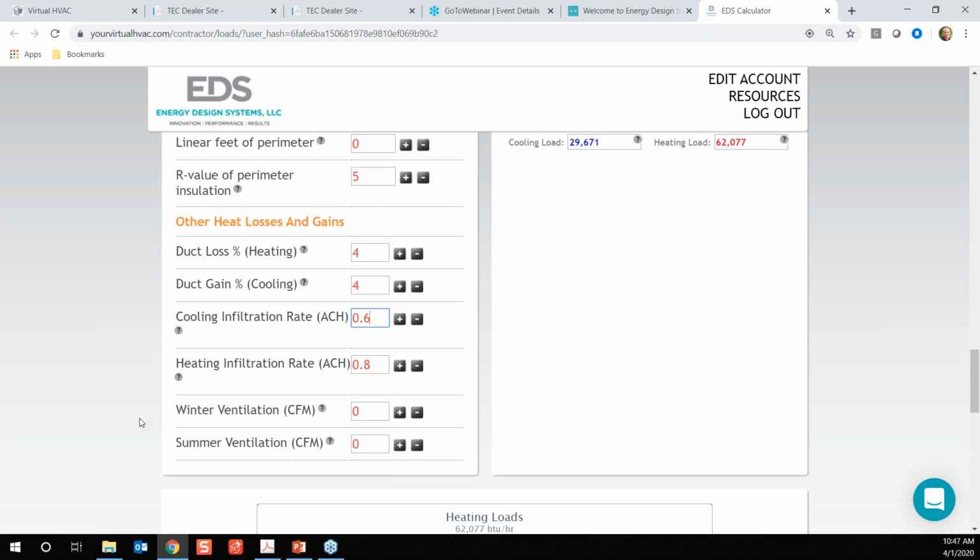And that's pretty common. Ventilation is air that I intentionally brought into the home. I sucked it in through a duct on purpose. Either I could be bringing that in through an ERV and then conditioning it, or I could be bringing it in raw, which is what we mostly do. So I have a 6-inch round coming into the backside of my furnace, which I actually do at my house. Actually, I think it's a 5-inch flex duct coming in from the outdoors to the return side of my furnace, and I'm sucking air in that way.